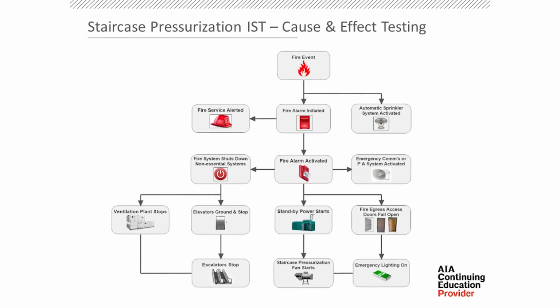Let's use this - here's how I explain it. When there's a fire event, a series of things happen: the fire alarm gets pulled, certain air handling units go off, the elevators ground, certain things come on and certain things go off, and this all happens in a certain order. The cause is the fire alarm pull, and the effects are this, this, this, and this. That's normally presented in a matrix format, and it has to be tested.